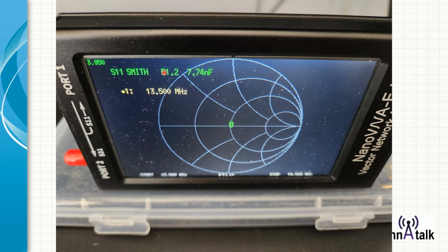So that's what you're looking for whenever you're doing a calibration or recalling a calibration for your frequency range, which will be down here from the start to the stop frequency. And you'll see an OSL, okay? That means open, short, load, and if you calibrate it for through, then you'll also see a T, and then you'll see a little C star that says it's been calibrated at that frequency range. So you should see that if you do a recall or a fresh calibration. So this is the way to sanity check if you've got a good calibration and a well-operating NanoVNA. If you don't see that, either you're doing something wrong or you have a problem with your Nano.